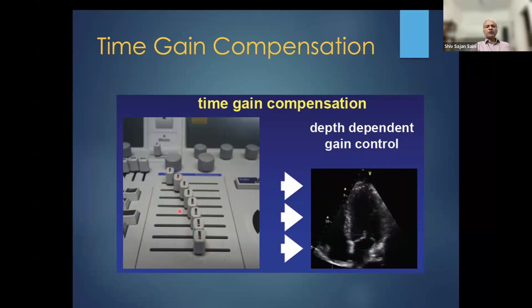So what I have done is I have minimized the gain, kept this knob on the extreme left end so that it is not increasing, or increasing to say only 10%, whereas this is increasing to much higher, maybe 60-70% gain of the deeper structures. So now if I throw the signals, I will see this image as a nearly homogeneous image, because of the differential gain for the deeper structures as compared to the superficial structures. So this is known as time gain compensation.